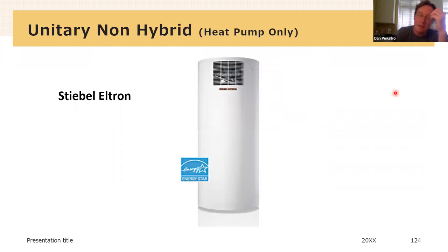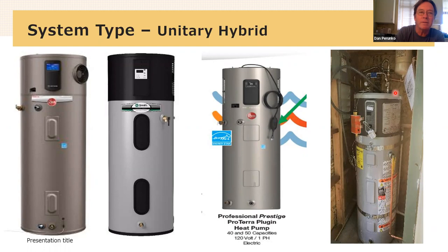This is a machine that's a unitary machine, and it's not a hybrid. Yeah, I did. I called these hybrids. For a second, I thought I'd forgotten to do that. In all of these machines, they have a heat pump and an electric resistance coil. The electric resistance coil's job is for makeup, right? Like the heat pump falls behind, the electric resistance coil turns on and it adds heating capacity. It draws a huge amount of power. So ideally, you don't want it to happen.